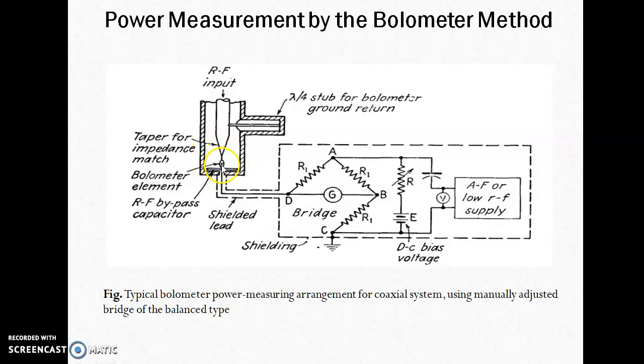The RF input comes from the coaxial cable and is tapered here to match the impedance with the bolometer element. The stub is only to complete the connection and return the signal to the ground of the circuit. Impedance matching is very important for maximum power transfer, and this is achieved by tapering the coaxial cable at this portion. There is also a bypass capacitor that isolates the DC bias circuit from the RF power.